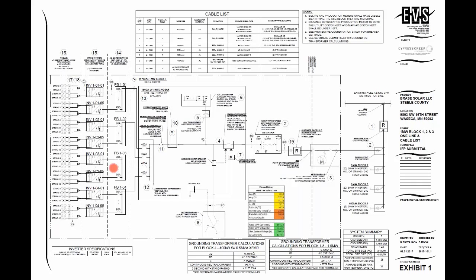In this case, group mounted breakers. They actually had a utility AC disconnect, so they could disconnect just the group mounted breakers. There was production metering. So this would be Xcel Energy provided CTs and an Xcel Energy meter that was internal to the switchboard. Yep, utility meter there. You had auxiliary load centers. So we had a station control power transformer, a group mounted little distribution panel for internal supply power for heaters, for protective relays, breaker power for metering, different monitoring there.